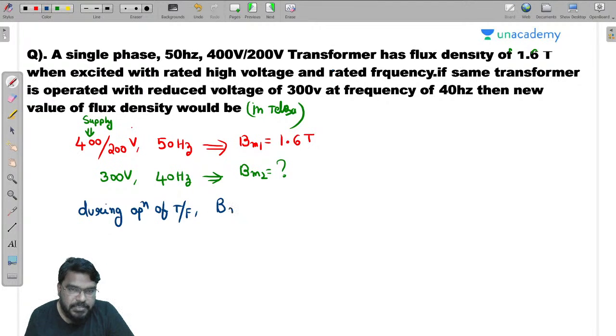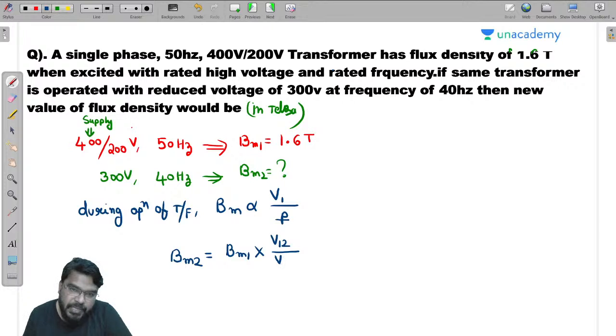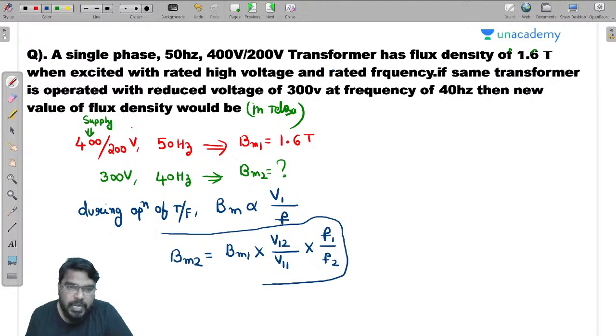So during operation of the transformer, maximum flux density is directly proportional to the V1 by F ratio. So we can write Bmax2 equals Bmax1 multiplied by V12 divided by V11, since it's directly proportional to voltage, multiplied by F1 by F2, since it's inversely proportional to frequency. This equation is enough to answer the question.